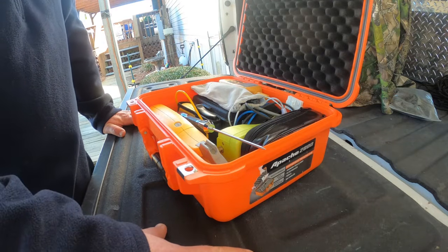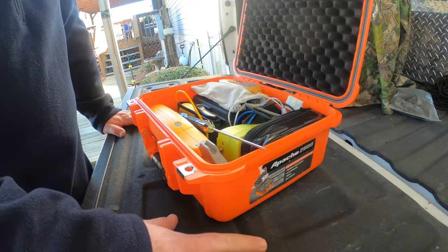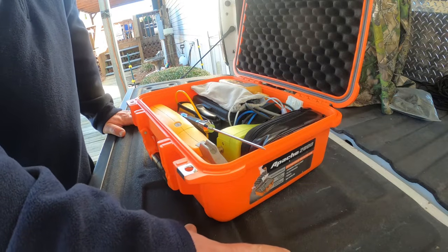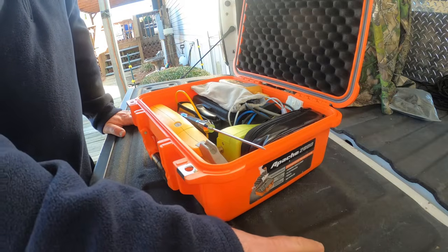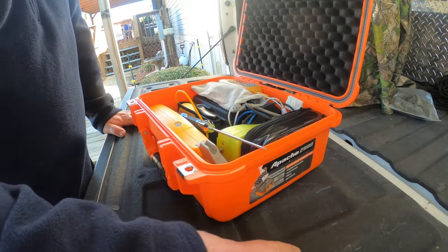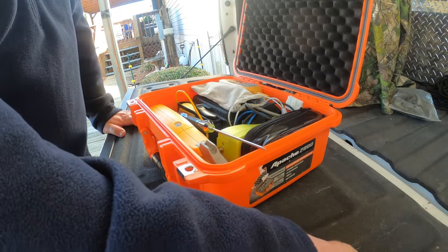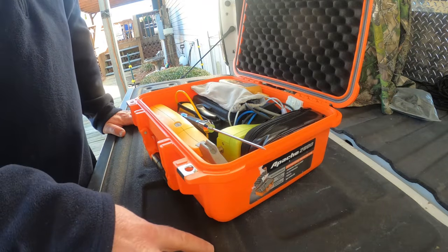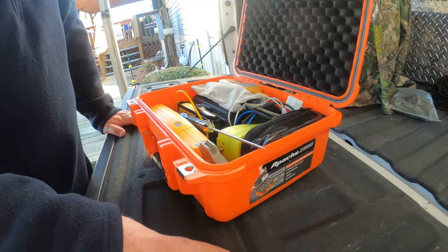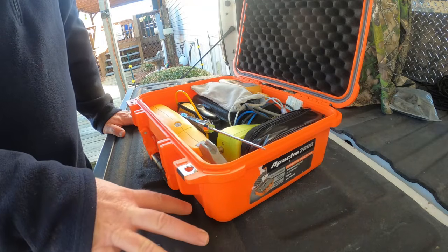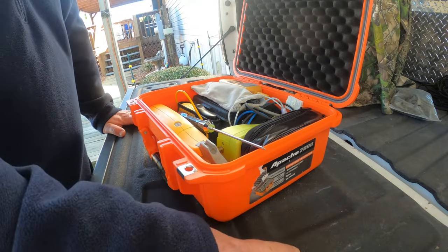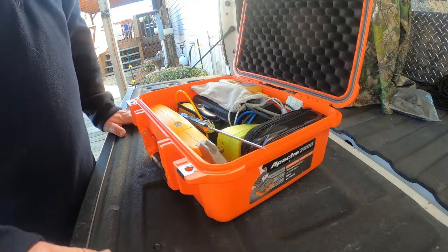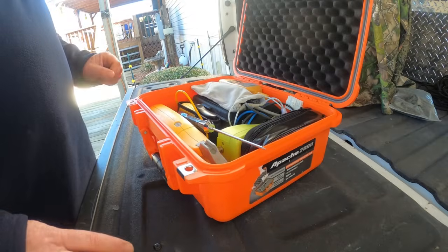They have a lot of videos on there on how to troubleshoot the Trane air handlers, doing the go or no-go test on the motors, checking with your DC voltage that you're getting the proper DC voltage for communications, and how to check to see if you're getting your data package sent from the board to the motor, and if that data package is being received back to the board from the motor. You're trying to determine: is my control board not communicating with the motor? Is the motor not communicating with the control board? So you can go there and find those videos.